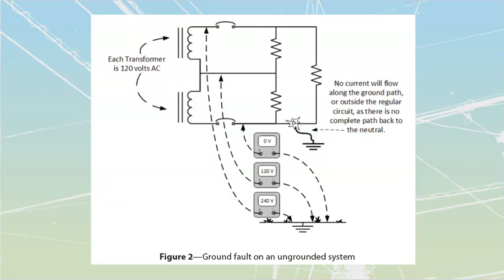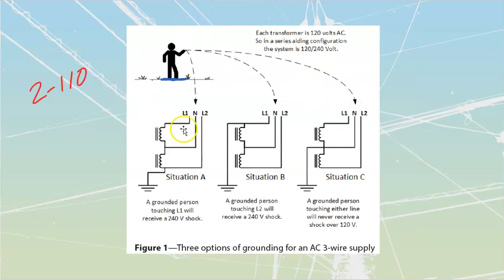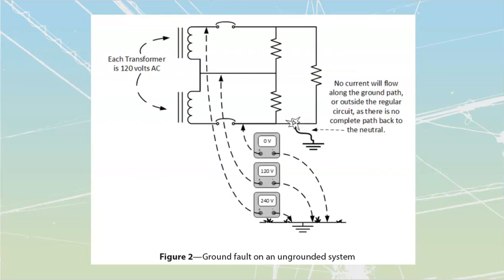The review section goes over the purpose of the ground, which is not only to minimize the potential voltage that we're going to be exposed to, it's also to help my overcurrent devices, or my circuit breakers, or my fuses, whatever I have inside of there, to operate. Over here they're showing an ungrounded system. If that ungrounded system has a fault off of it, there is no place for fault current to flow. So if there's no place for fault current to flow, that system, which would have been a floating or an ungrounded system, is just going to idle along. There's not going to be any difference other than we're going to see different voltages across 0, 120, or 240.